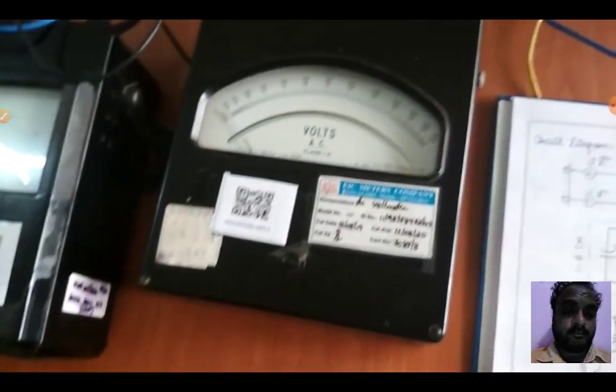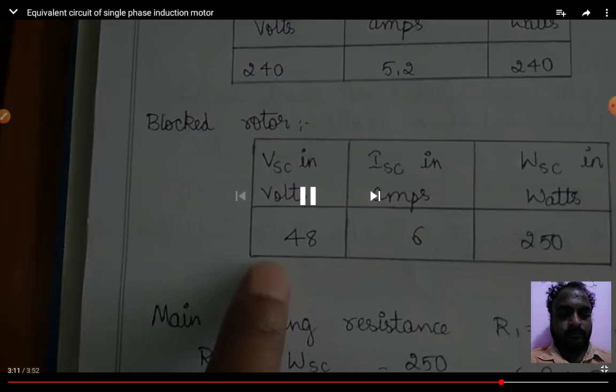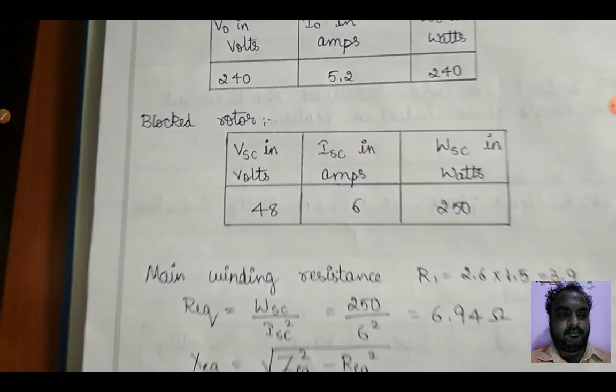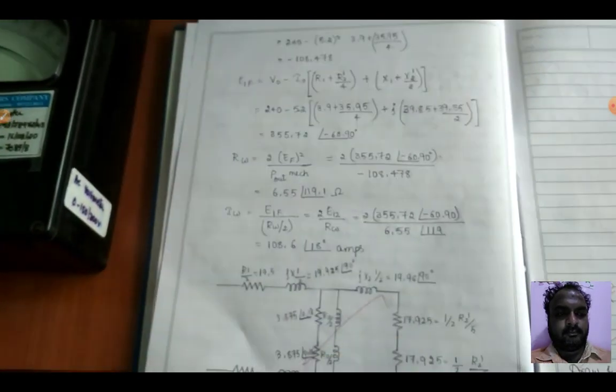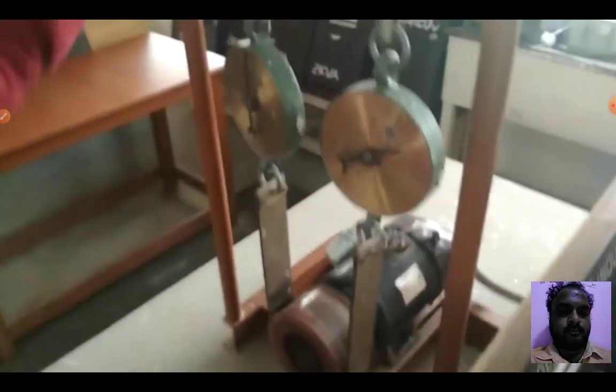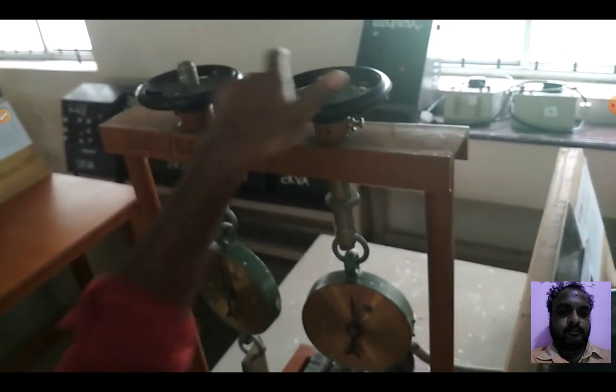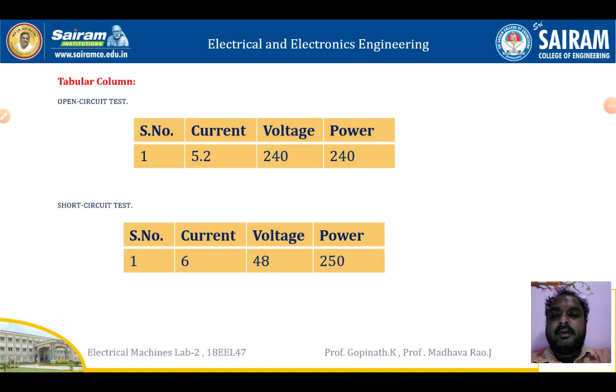Note down the wattmeter and voltmeter readings in the blocked rotor test tabular column: voltage, current and power. Similarly, calculate the parameters and draw the equivalent circuit of the induction motor. So bring back the auto transformer to zero position, release the load on the induction motor and switch off the main supply. So this is the demonstration of the experiment.